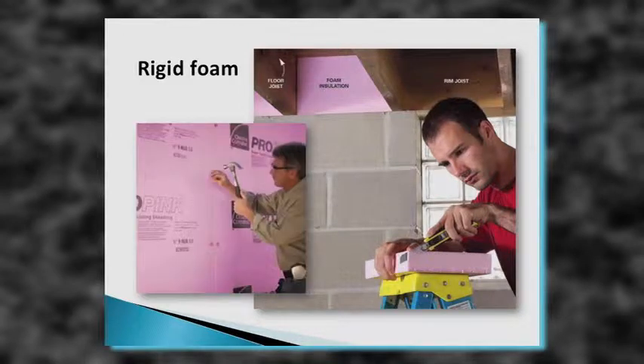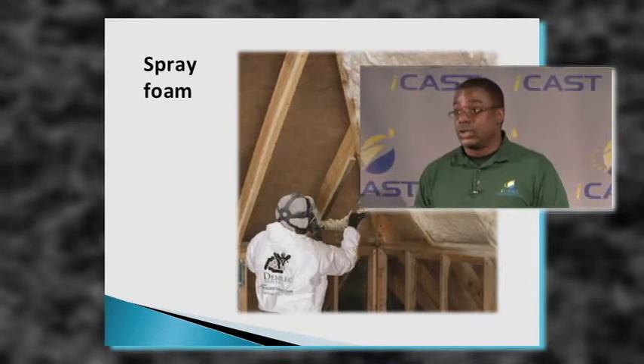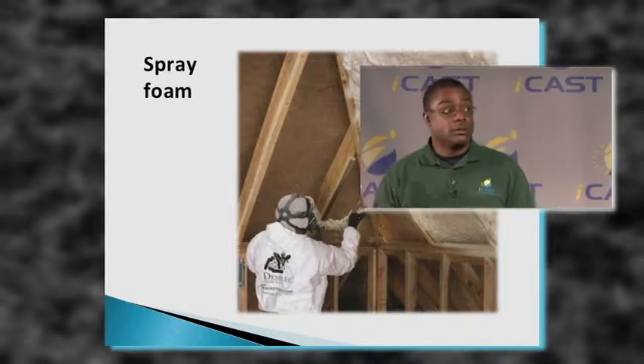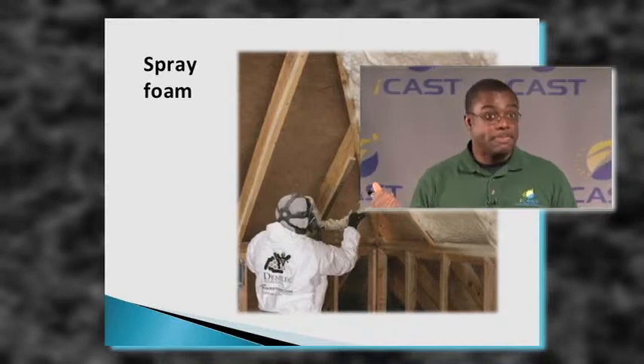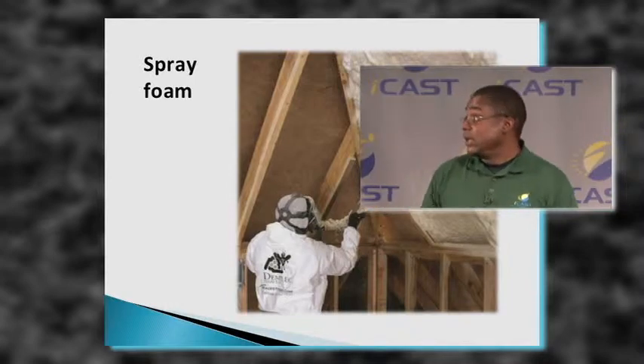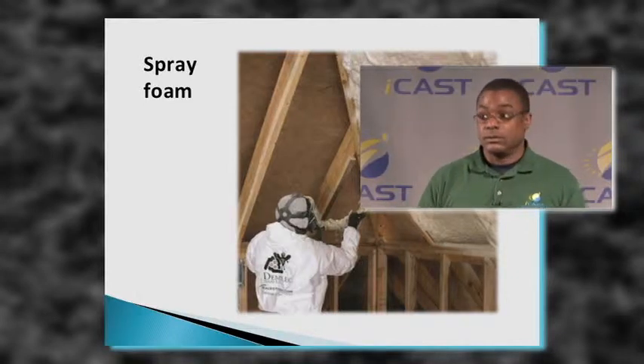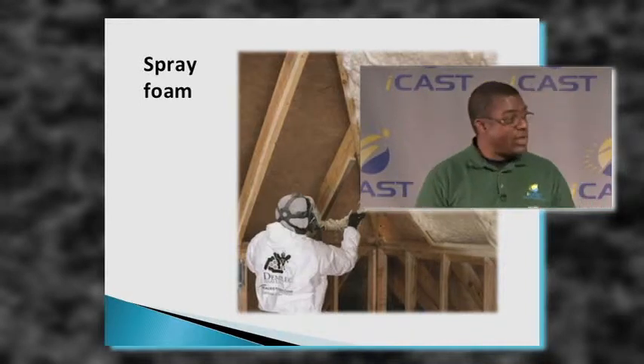Even when you put foam board on the outside, you also put insulation in the walls behind it — that provides additional thermal resistance. Notice the worker installing spray foam is geared up with full PPE including a supplied-air respirator, not just an air-purifying respirator. Spray foam has excellent insulating properties — upwards of R-7 per inch.